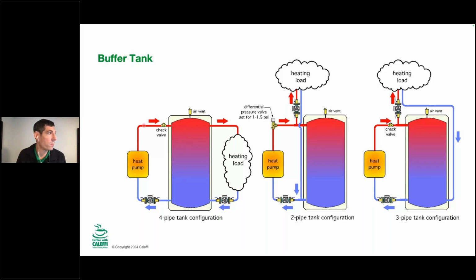The better way to do that would be to pipe the indirect tank off of this side, so we can just have the boiler or the heat pump heat up the indirect tank, and then the buffer tank in the middle of summer does not need to be 180 degrees if the heat loss calculation, the outdoor reset curve says we only need 110 during the summer. No need to heat that whole thing. So that's a limitation of a 4-pipe. You're going to have some mixing there. So these two examples are a little bit trickier, just as far as the piping goes that you look at here. There's a little bit more complexity. What this allows you to do is send the hottest water from the heat pump directly out to the building. So you can go direct to load here.